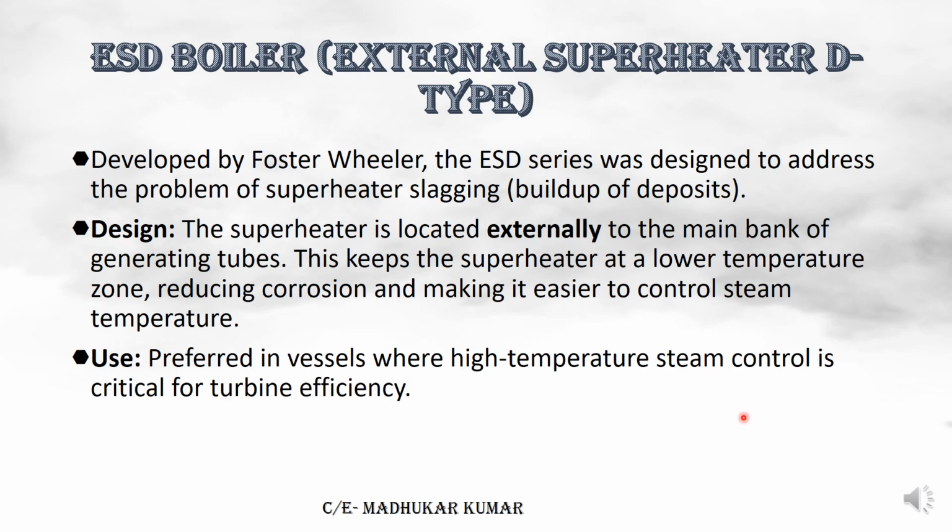ESD, external superheater, basically for the propulsion system when we are using turbines. So superheaters are attached. This type of boiler, ESD type, basically addresses the problem of superheaters fouling, buildup of deposits in them. The superheater is located externally to the main bank of the generating tubes.